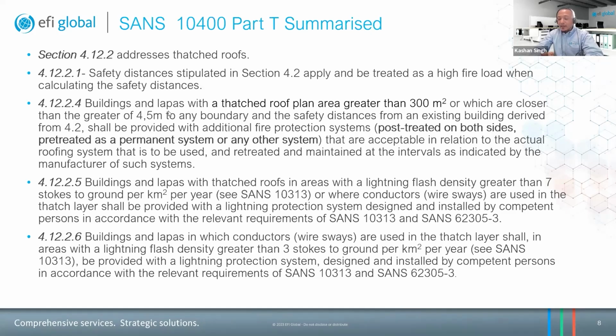Now, your calculation on your safety distance to any boundary or adjacent building does vary depending on how your roof is treated. But again, I'm not going to jump into the calculations. I feel that's unnecessary for this presentation. So buildings and LAPAs with a thatched roof plan greater than 300 square meters, or where it is closer than 4.5, just summarizing, to the boundary, and the safety distance from an existing building derived from 4.2, the table where we see the minimum stipulated distances, shall have additional fire protection systems, that being post-treated, the thatch itself post-treated on both sides, pre-treated as a permanent system, or any other system.